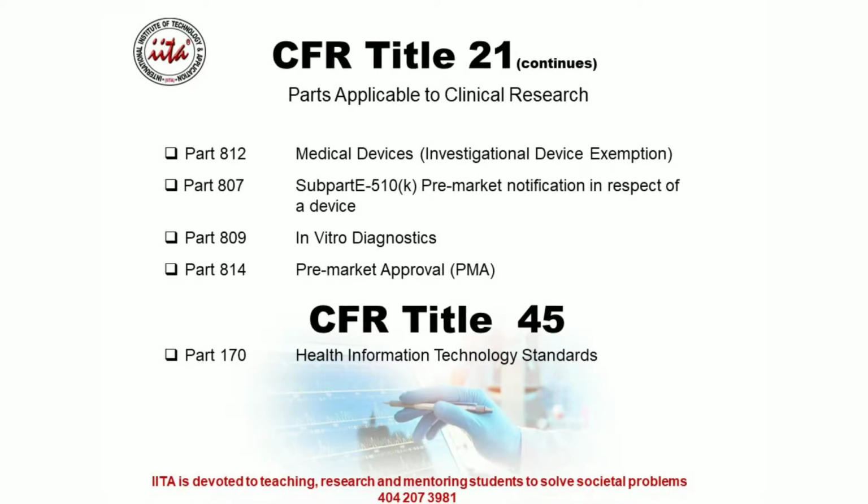CFR Title 21 continued. This includes Part 812 for medical devices, Part 807 for pre-market notification in respect of a device, Part 809 in vitro diagnostics, Part 814 pre-market approval. Then we have CFR Title 45, and that includes Part 170 for Health Information Technology Standards.